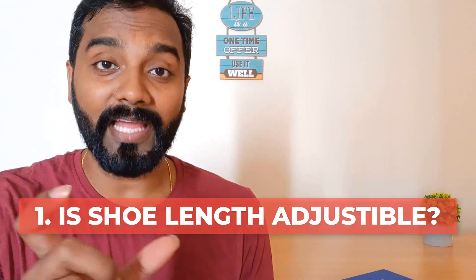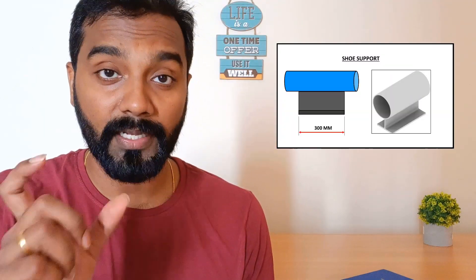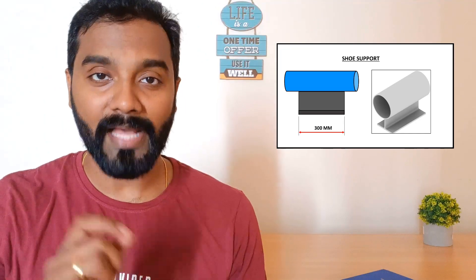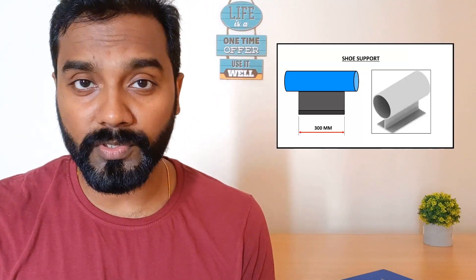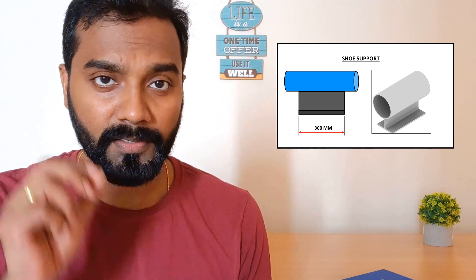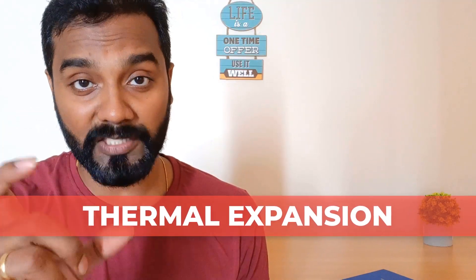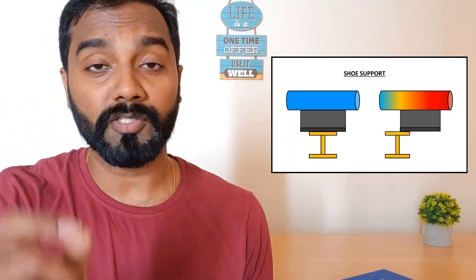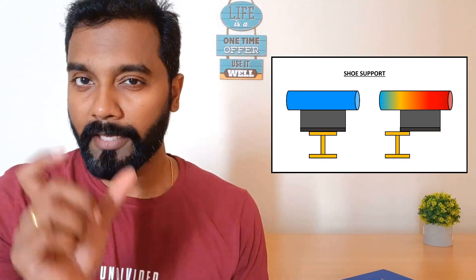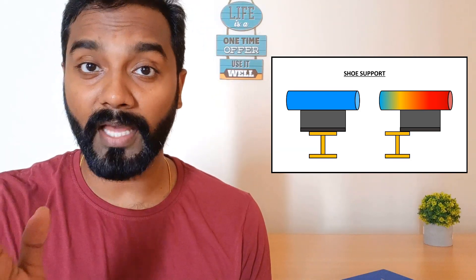Point number one: can we change the length of the shoe support given in the pipe support standard? If you look at any standard across the world, the length of shoe supports given in the standard would be 300 mm. The length of shoe supports is designed based on various factors. One very important factor is the thermal expansion of the piping. If the pipe tends to move from one point to another during thermal expansion, the pipe support has to ensure that the pipe still remains over the structure or beam. If the length of the shoe support is less, it will slip away from the beam and cause a lot of sagging.